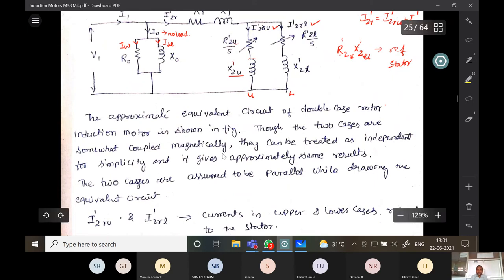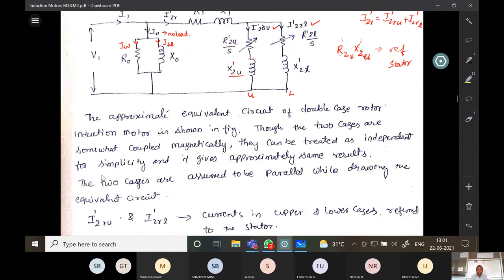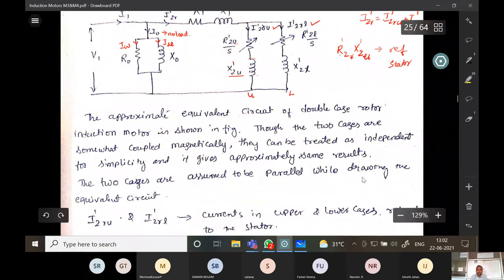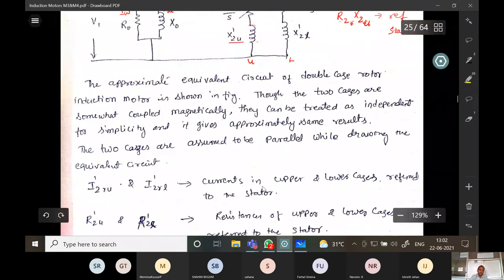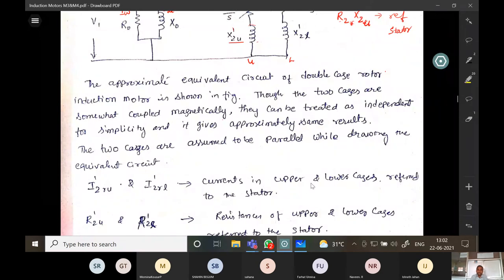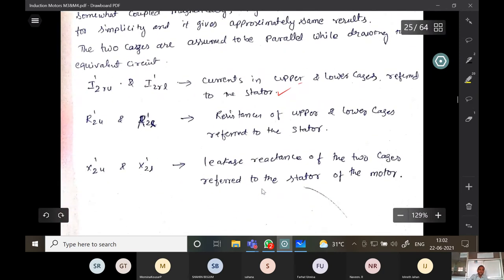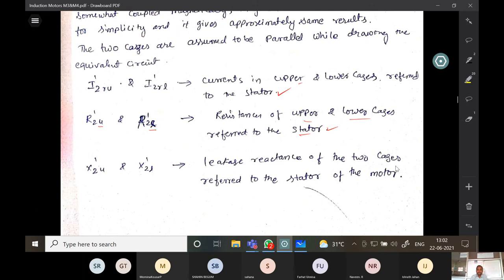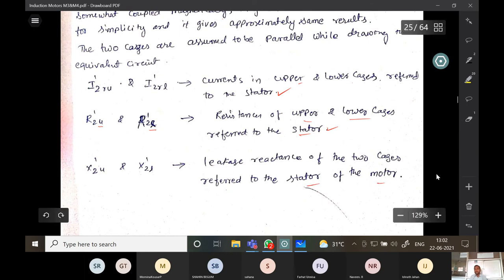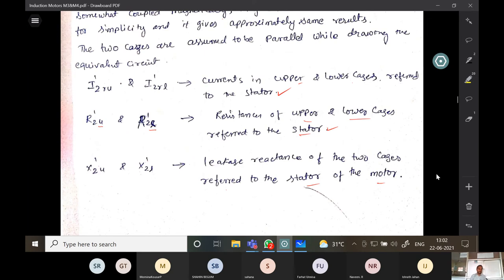Though the two cages are somewhat coupled magnetically, they can be treated as independent for simplicity, giving approximately the same result. The two cages are assumed to be in parallel. I2R dash = I2R dash U + I2R dash L, and resistances are R2U/S and R2L/S. X2U dash and X2L dash are the leakage reactances of the two cages referred to the stator. This is the equivalent circuit for performance evaluation of the double cage rotor.